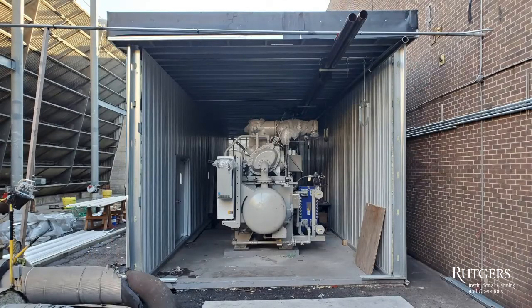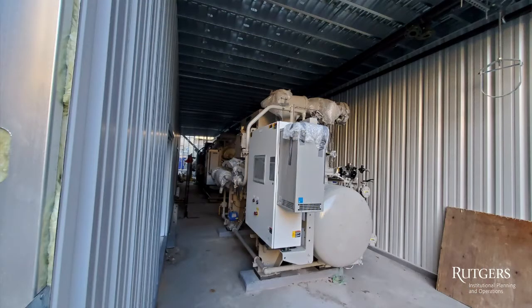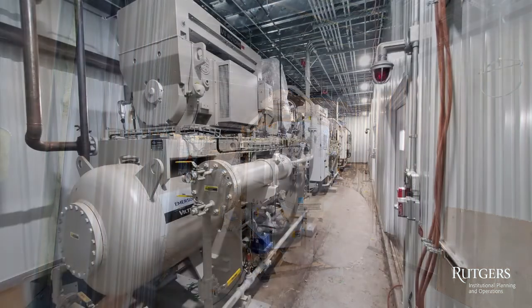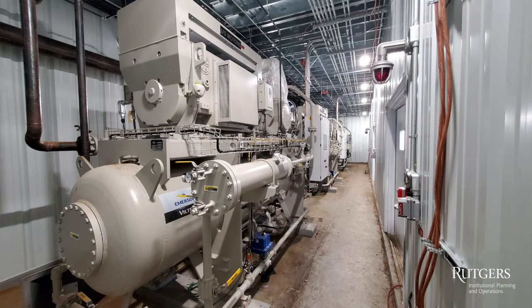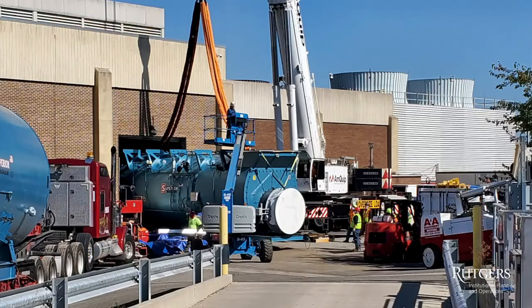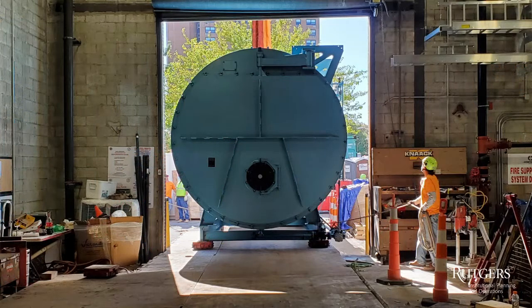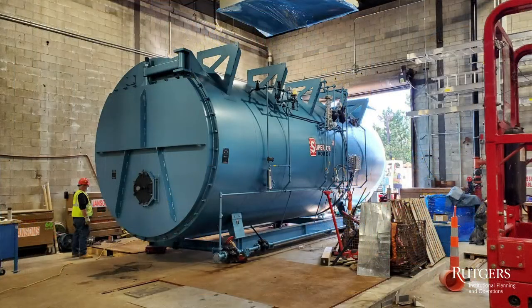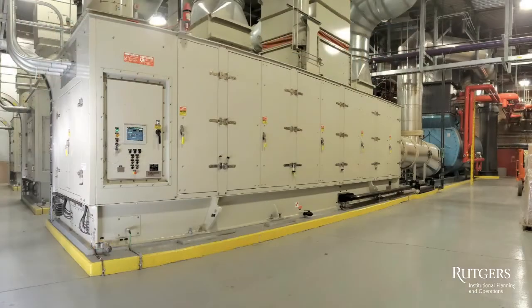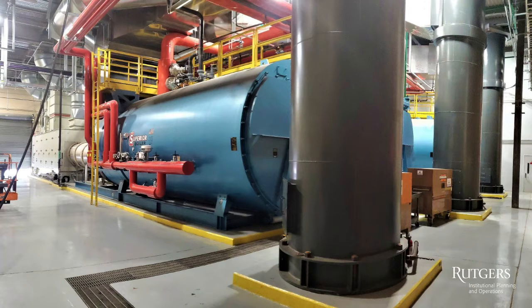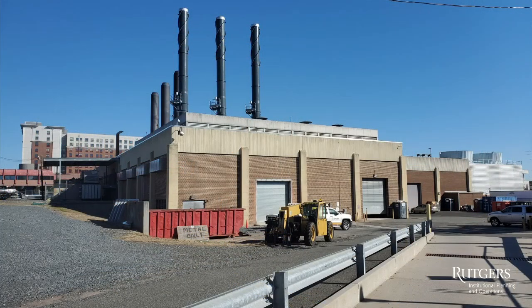In Newark, we had put in new gas compressors because we received gas at 15 pounds, and the turbines use 200-pound natural gas pressure. The heat recovery steam generator in Newark and the heat recovery hot water boiler in Busch were replaced, and both were installed with new booster burners or duct burners that would allow us to produce all of the steam that we needed or could out of the machine. In addition to that, in Newark, we replaced all of the high voltage main switchgear within the plant. So those are basically upgrades on that.